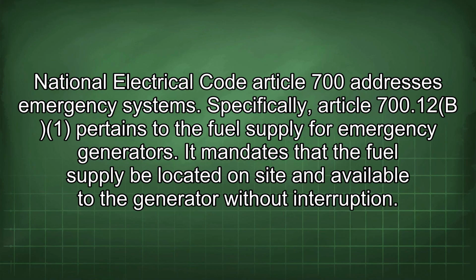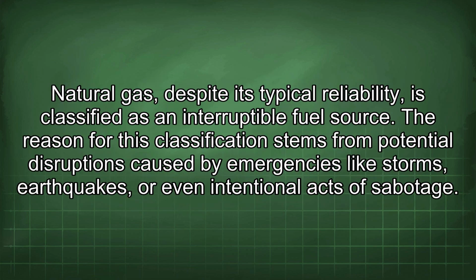National Electrical Code Article 700 addresses emergency systems. Specifically, Article 700.12 pertains to the fuel supply for emergency generators. It mandates that the fuel supply be located on site and available to the generator without interruption. Natural gas, despite its typical reliability, is classified as an interruptible fuel source.